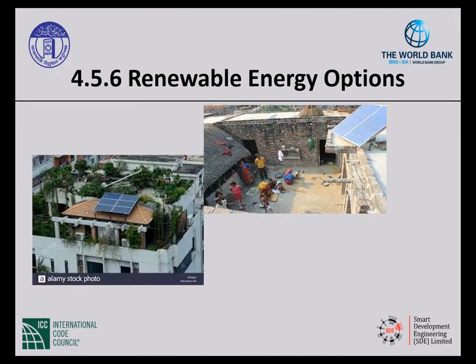Section 4.5.6 brings in some renewable energy options. So there's options, but they're requirements. Right? So they're different for residential than they are for all the other occupancies. 4.5.6.1 tells us that buildings of occupancy A, those residential occupancies, have to have solar or other renewable sources of energy to power 3% of the total electric load of the building. So for residential, you need to provide solar or other renewables to power 3% of the total electric load.